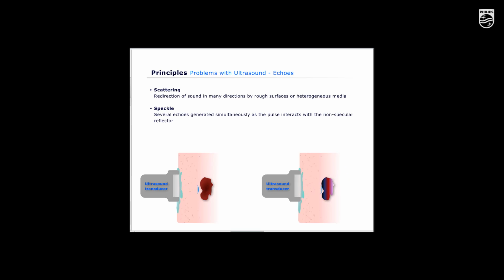Another problem with ultrasound is the scattering of the sound or redirection of the sound in many different directions as shown in the animation. Speckle is the generation of multiple echoes in different directions when the ultrasound hits a reflector. Both of these happen all the time in ultrasound. Fortunately, however, the ultrasound systems are made to minimize the effect of these. When we talk about reflectors, there are two main types. There is a specular reflector, which has a nice smooth surface, and a non-specular, which has an irregular or jagged surface. Reflected waves from these interfaces can scatter out in many different directions.